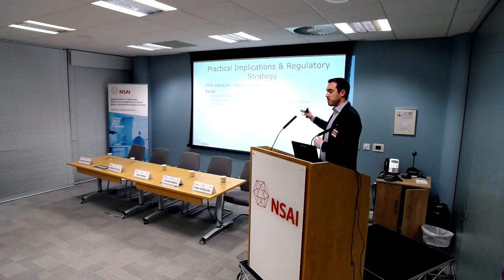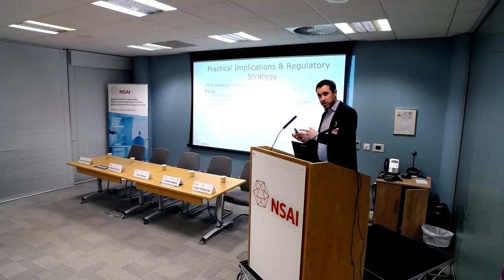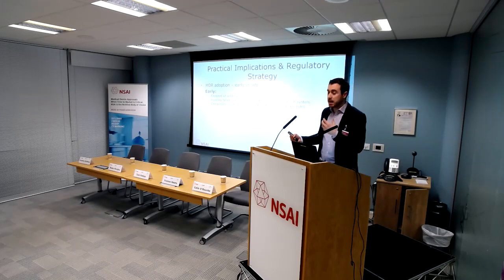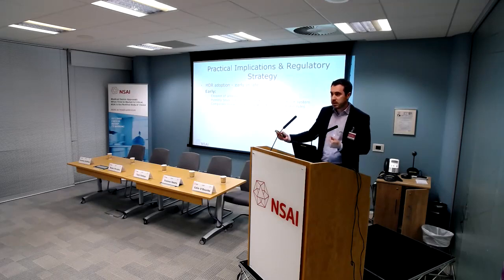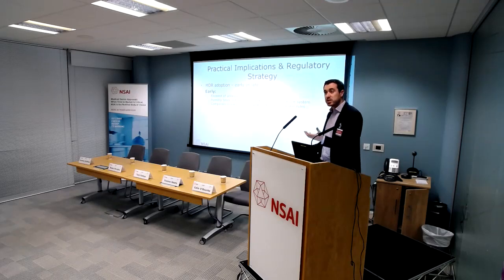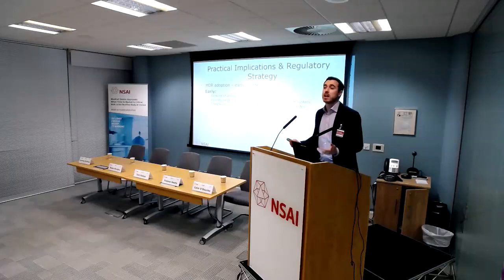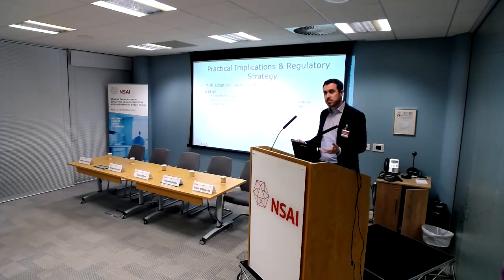So what I mentioned in one of my earlier slides about products that can remain on the market under the MDD out to 2024 still have to comply with some MDR requirements from 2020. So you've got a tech file that is complying to the MDD and is actually also complying to some elements of the MDR. And how is that going to be managed by your quality system? So that's a consideration as well.